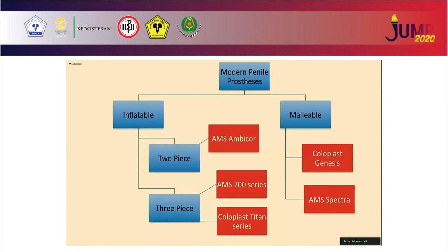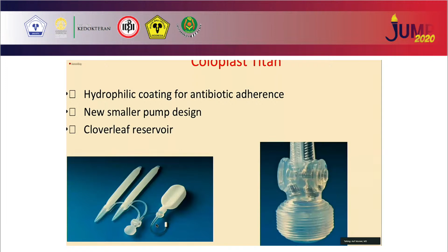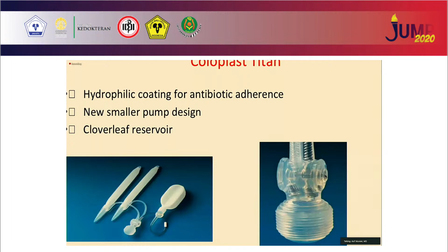So here is the Coloplast Titan, and you can see here on the left, you've got 2 cylinders connected to a pump, and you've got a reservoir here with a lockout valve, so you don't get fluid going in and out spontaneously. On the right, you can see the pump. You can see that you've got the bulb at the bottom to squeeze to get the fluid from the reservoir into the cylinders. And then you've got this little nib over here that you press to deflate the implant once you've used it. So this is the same principle.